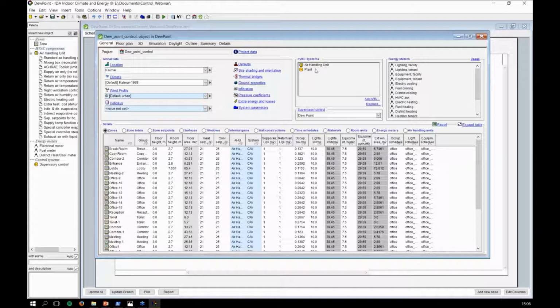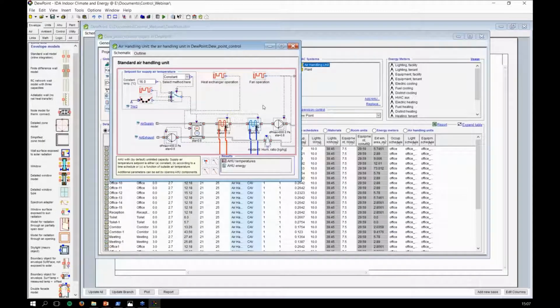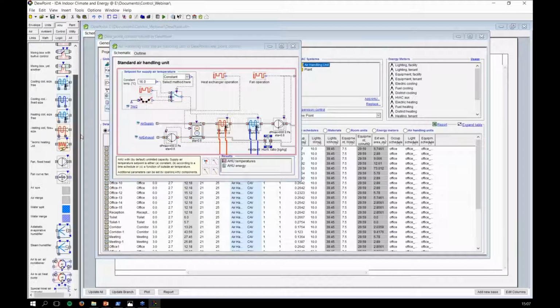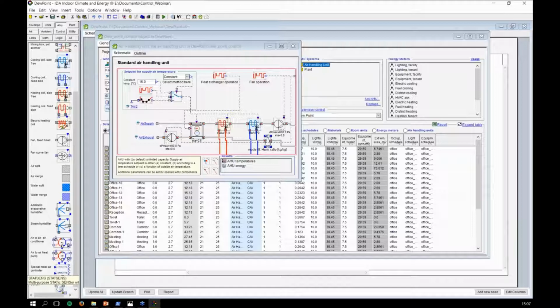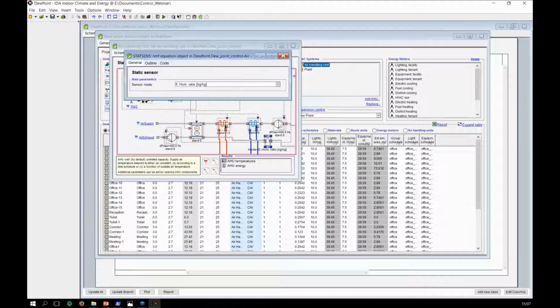And now for the dew point control, one way to do this is to take a representative amount of humidity that is located inside the building, and based on that, shift the temperature of the set point for cooling for the zones, right? So our typical user would, for instance, open the air handling unit, and he would put a temperature or humidity sensor on the return air side. So this sensor here you will find in the air handling unit panel here. If you drag this all the way down to the lower, you find this state sensor. And if you drag it and double click it, this sensor allows you to basically log several things, 10 options.